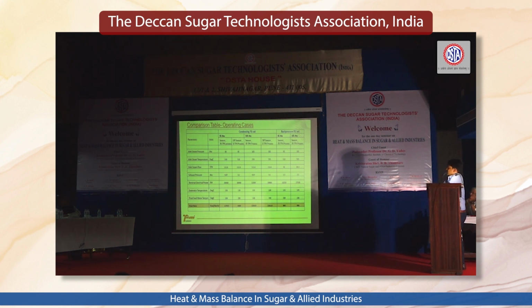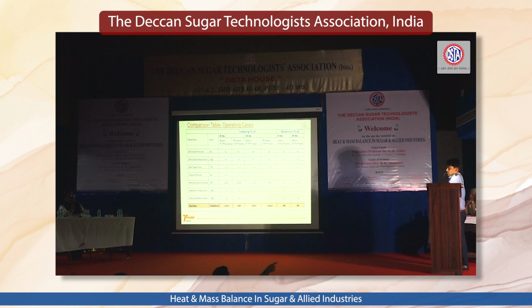Go back one slide. This is a typical 5000 TCD plant with a 70 TPH process, worked out with two regenerative HP heaters and 2.5 as the process parameter. This is the back pressure case, but the disadvantage is that this turbine cannot be operated during the off season. It can only be operated seasonally.